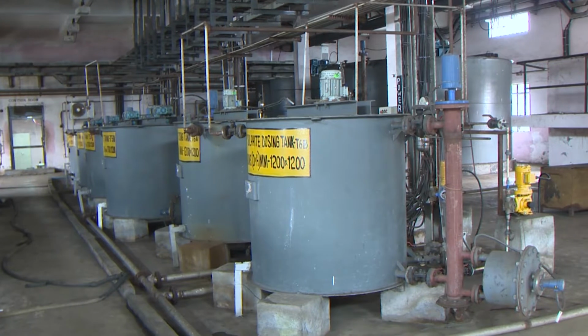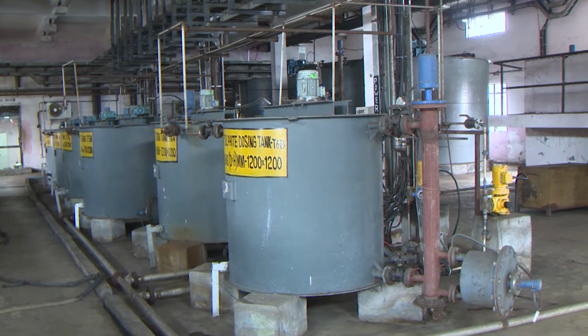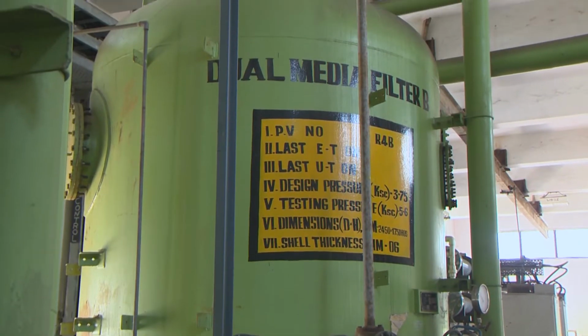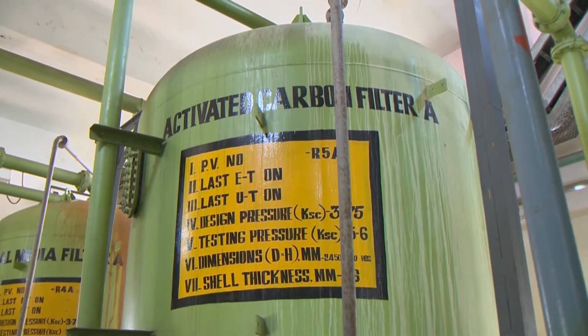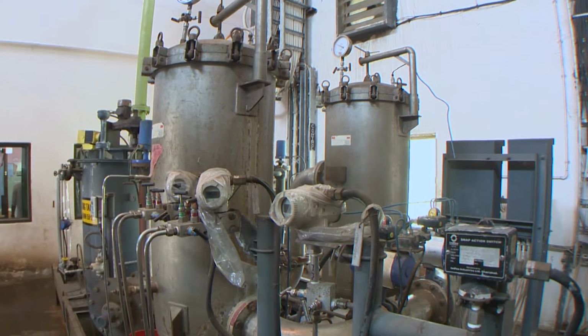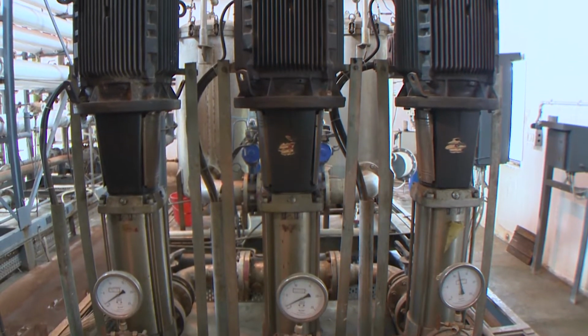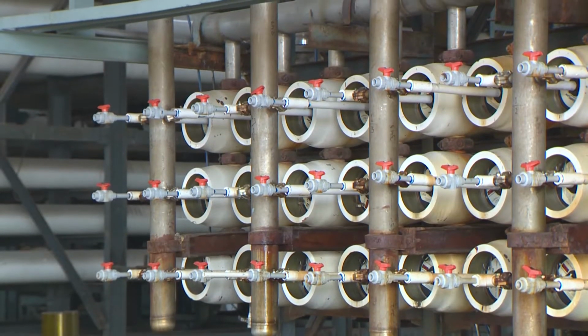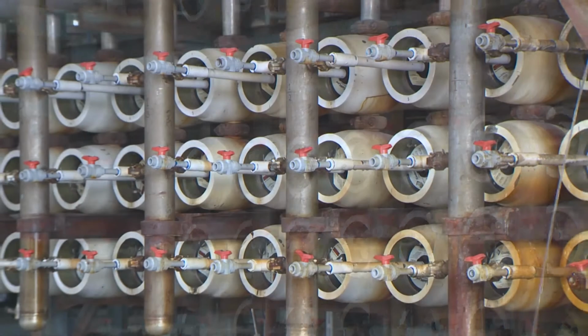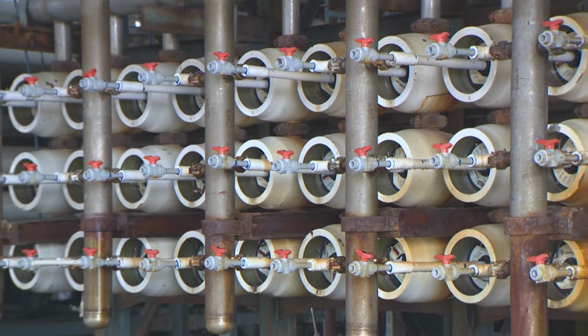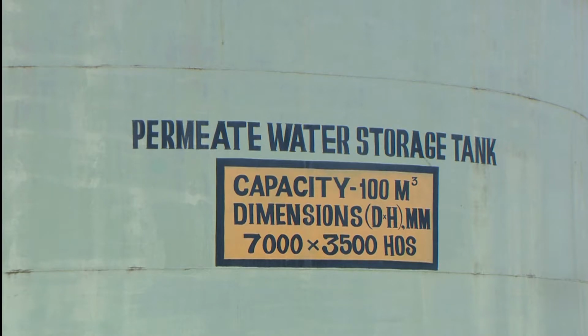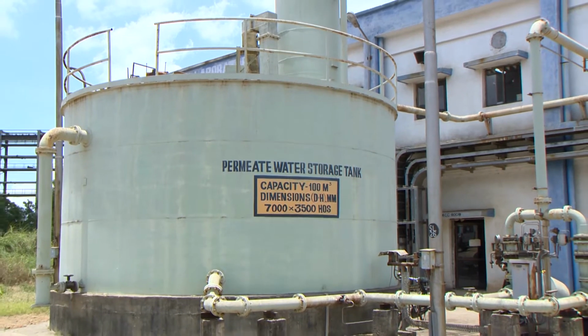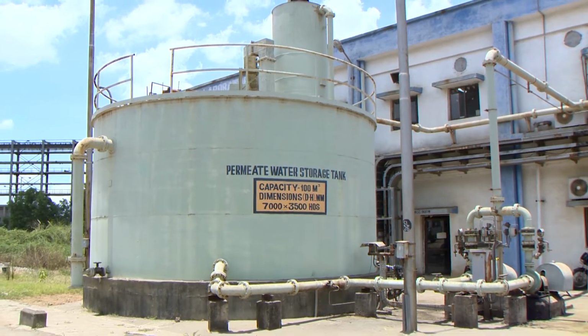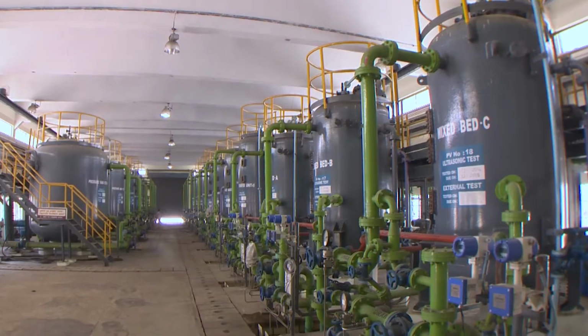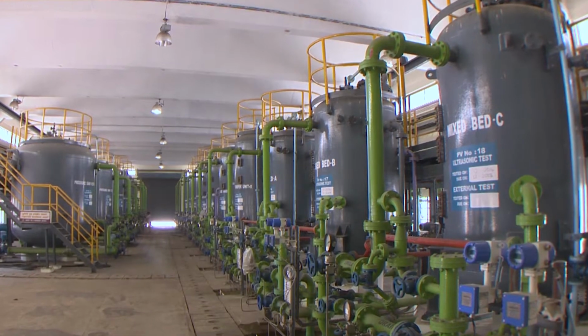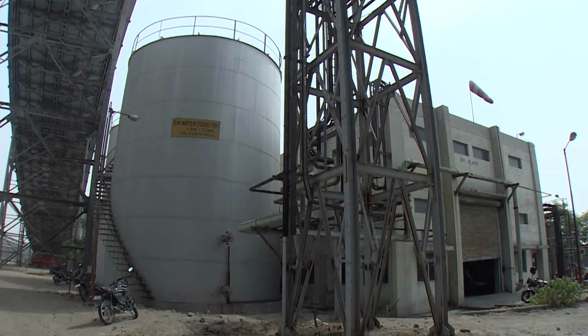The other part of DM clarifier water is pumped to RO plant through dual media filters, activated carbon filters and micron cartridge filters. Then high pressure RO pump supplies the water to RO modules arranged in two streams. The treated water from RO modules is stored in permeate water storage tank. Then DM plant supply pump supplies the permeate water to mixed bed to produce DM water with required quality and stored in DM water storage tank.